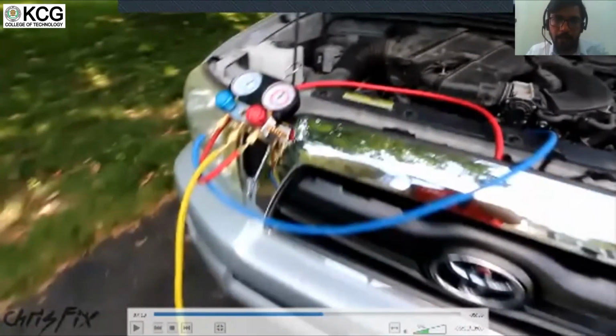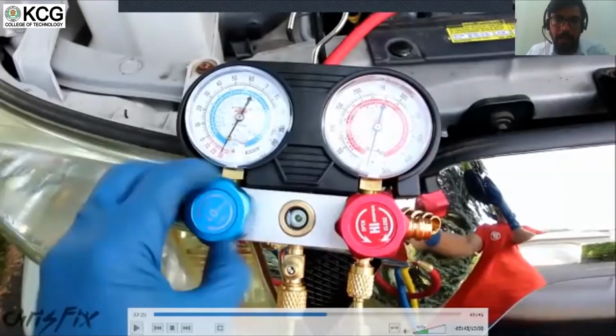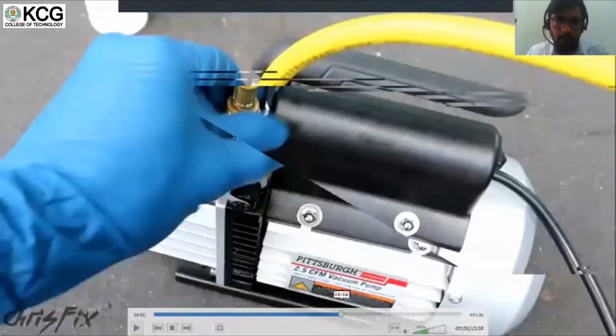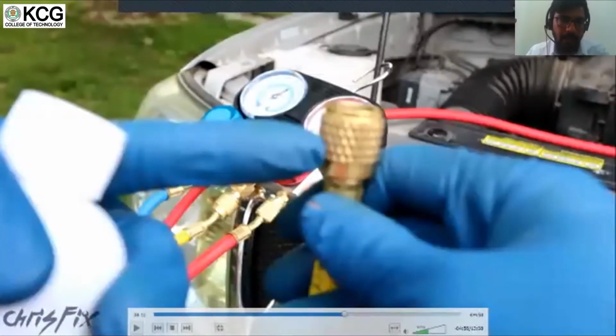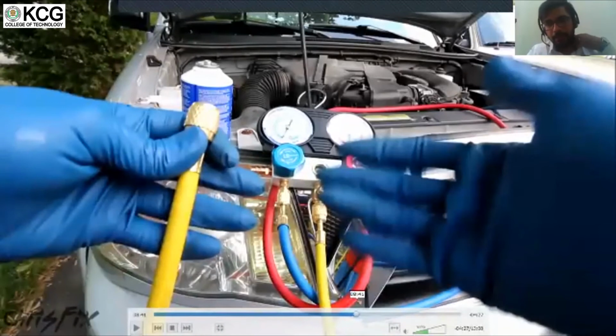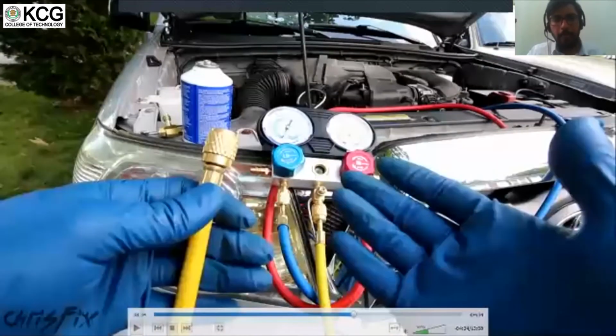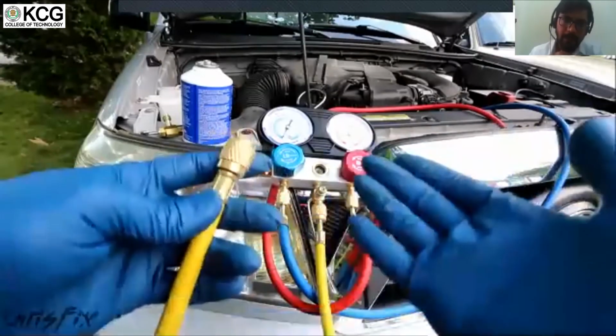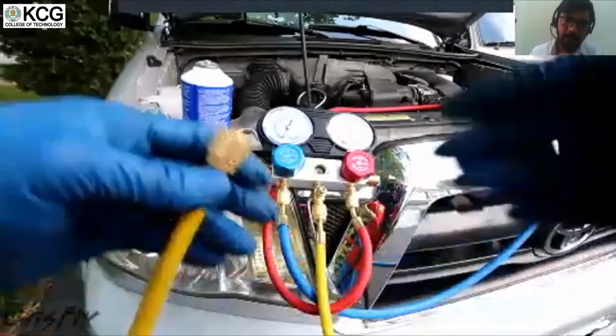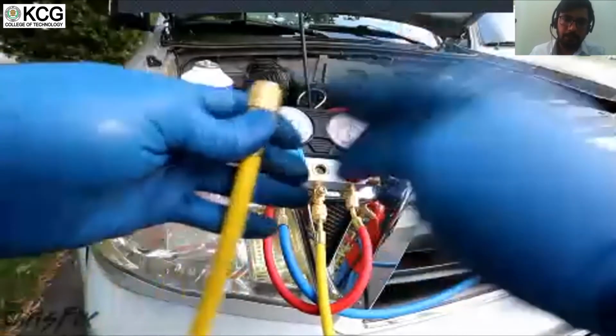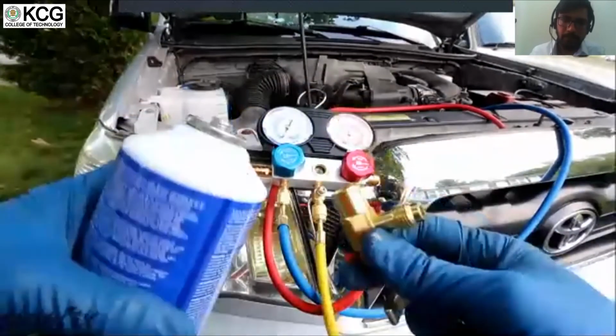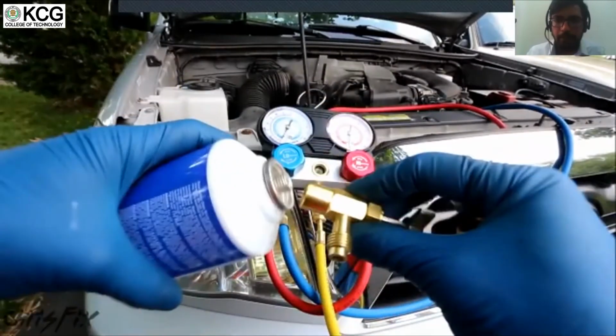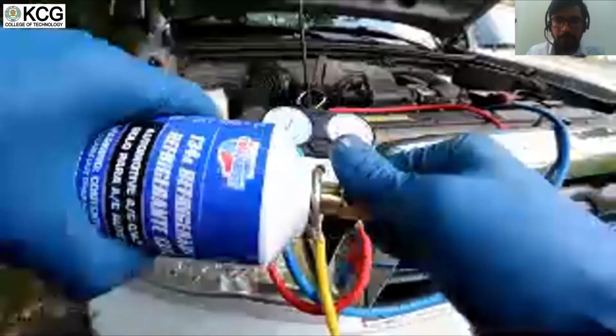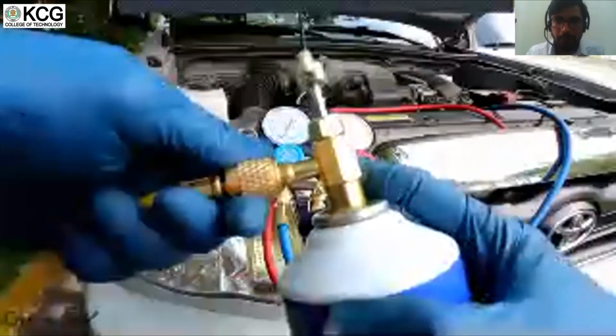So at this point it is detached, and now this guy will be attaching the refrigerant. I did the leak detection video, it's in there, so we don't have to do that. In this case, I don't have to add oil, it's already pre-oiled, and I don't have to add UV dye, I already have it in there. So now we're going to connect our refrigerant to this line. The first thing we'll do is connect our refrigerant can. Make sure it's a nice tight seal. Now we're going to connect our refrigerant can to our yellow line.